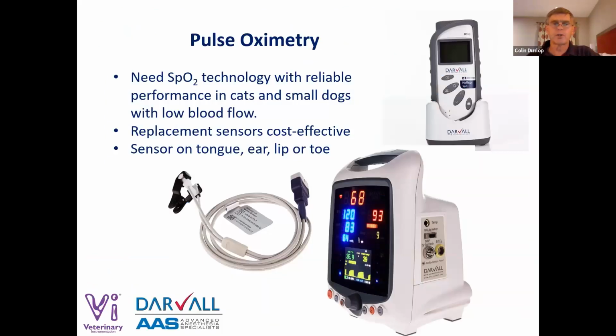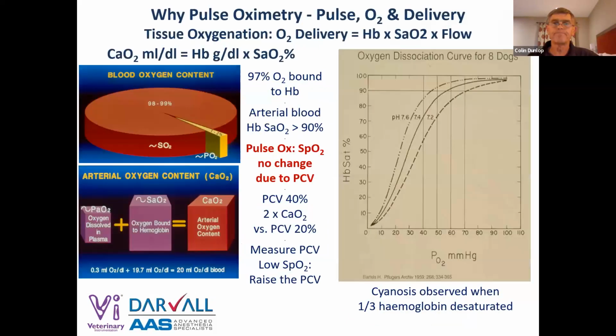So let's talk about pulse oximetry first. Pulse oximetry is a relatively simple concept in terms of what we do. We have a sensor that transmits red light and infrared light through the tissue, picks it up on the other side, reads the light absorption, turns that into a pulse and an oxygen value. There's more smarts in a pulse oximeter than there probably is in the old DVD player or VCR player that was attached to your television. So there's actually quite a lot of electronic processing in one of these things to make it work.